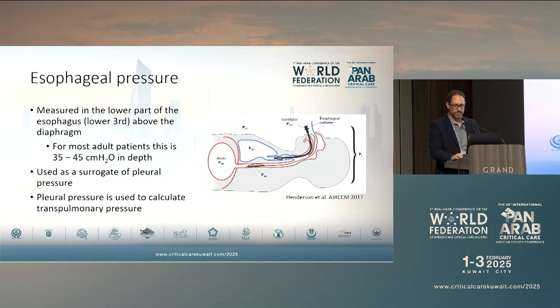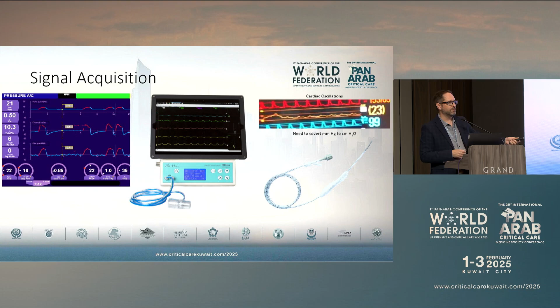The esophageal waveform can also be brought up on the screen, but in real time you get this idea of the dynamic stress on the lungs. There are also available bedside monitors that, if you don't have the integration, you have the pressure flow transducer and a catheter and a standalone device. And if you want to just measure pressures, you can use an ICU monitor with a catheter and a transducer, but it does require converting millimeters of mercury to centimeters of water for doing calculations related to the ventilator, but you lose the ability to monitor things such as asynchrony, which I'll talk about later.